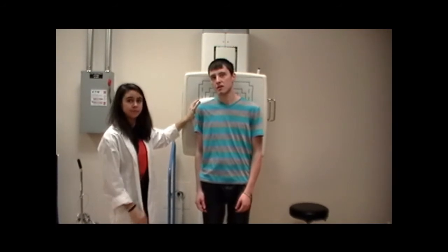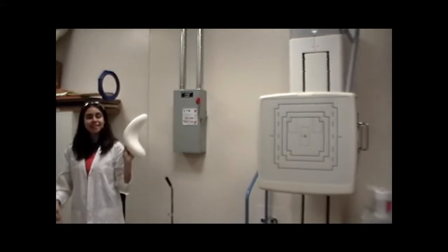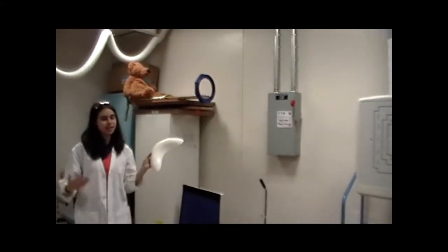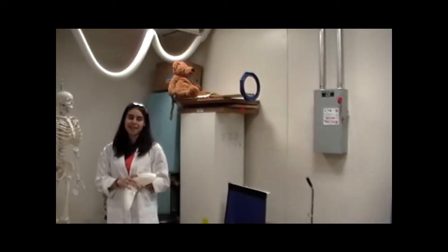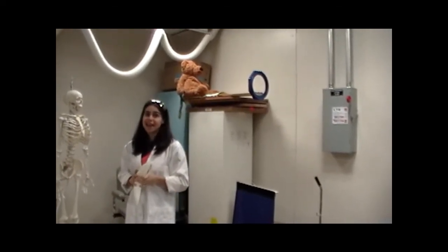We need these types of filtration to get rid of those low energy X-rays. This increases the average beam energy, allowing more to transmit through to the image receptor and accurately represent the anatomic part. The less dose received by the patient is following best practice and the principle of ALARA. Recall that off-focus radiation is radiation that doesn't hit the focal spot on the anode.